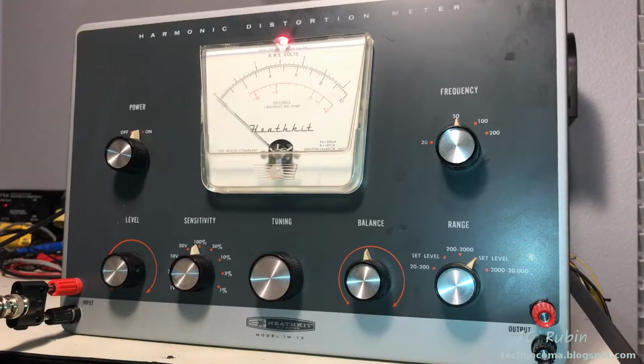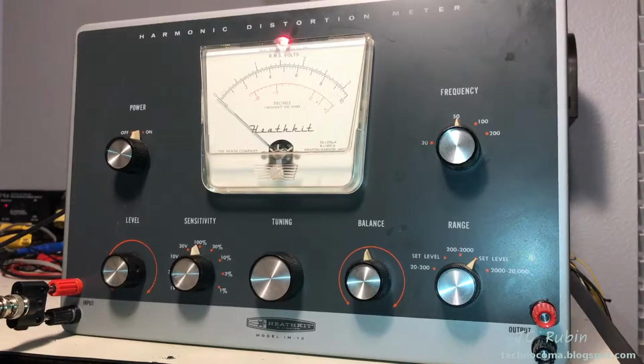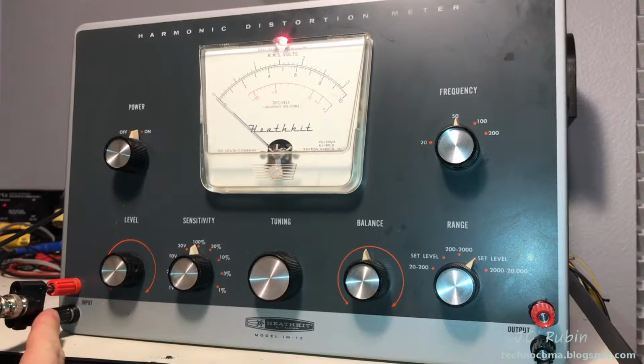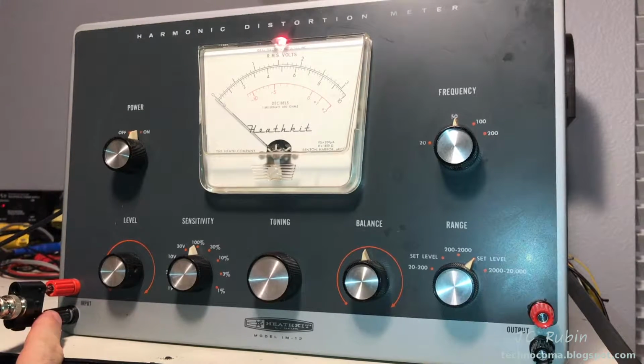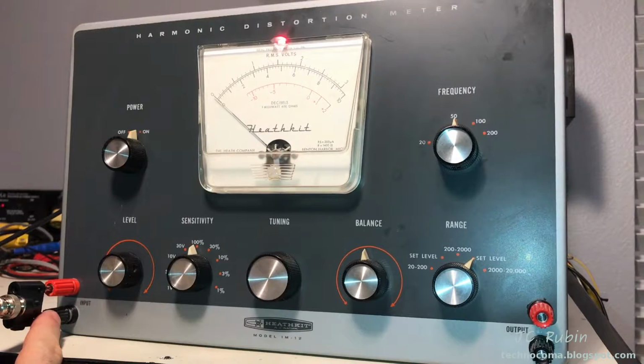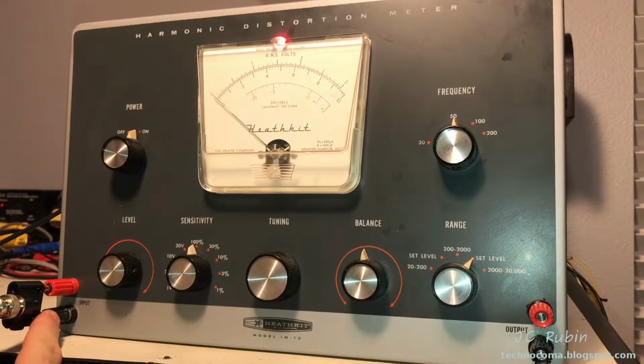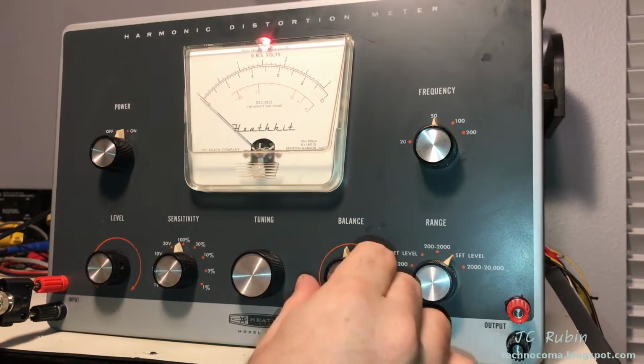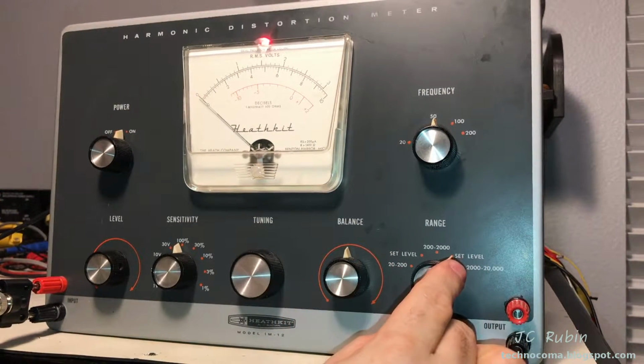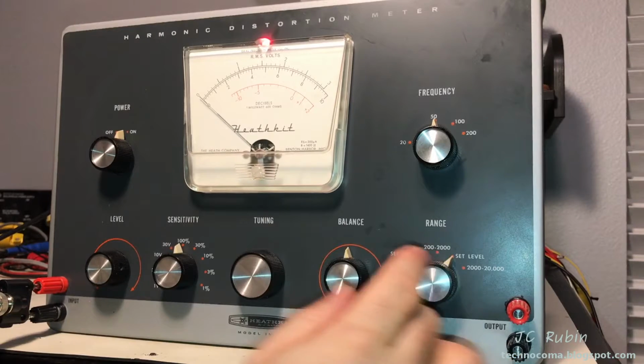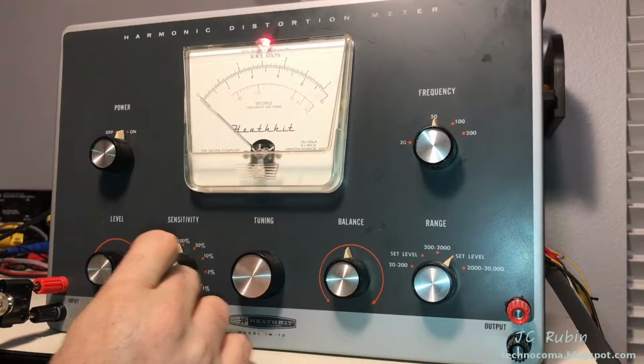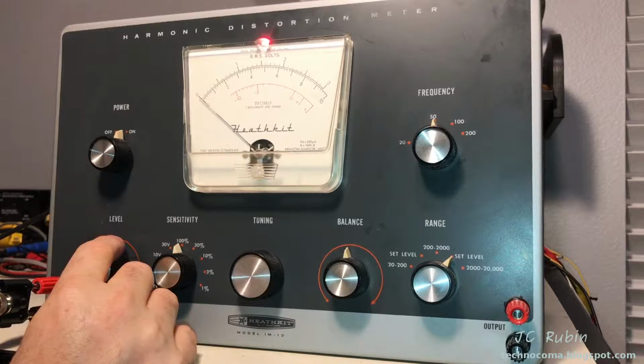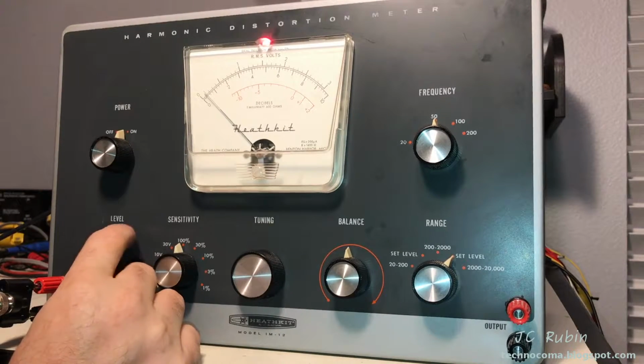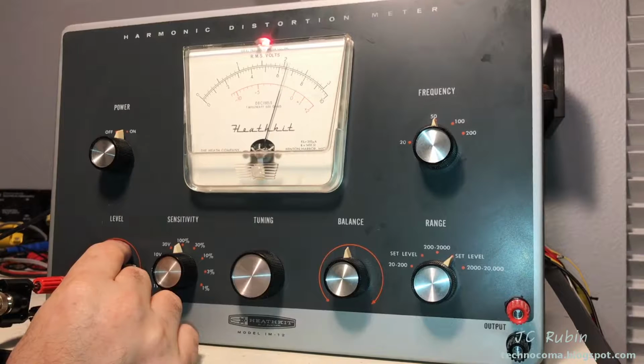Now we'll start with the next adjustment, which is the balance adjustment. And I will point out that I am using the Feeltech, which is running a 2 kilohertz sine wave into the input right here, and I have set it at 1 volt. It says to use your discretion and set it at least half a volt, and I found 1 volt to be sufficient. We ensure the balance is in the middle. Range switch is at set level. Sensitivity sits at 100. And we will turn the level knob here to 100% deflection, or full scale deflection as it were.